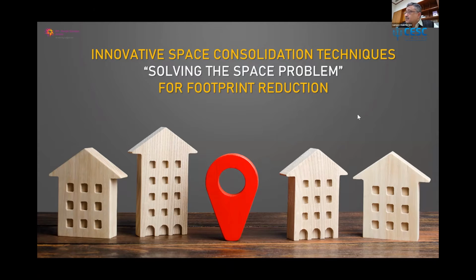So what we do is, within the same space, through prudent engineering, we upgrade existing stations from 33 kV to 132 kV, or from 132 kV to 220 kV, so that in the same footprint we can handle more power, and demand growth can follow our network addition - which is another key to remaining resilient and robust.